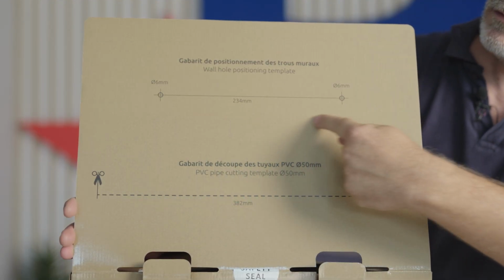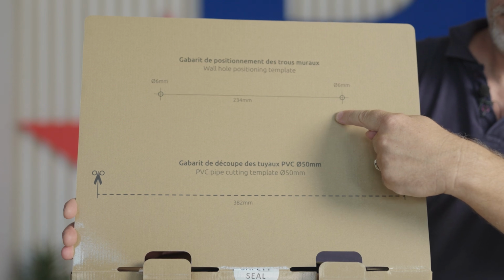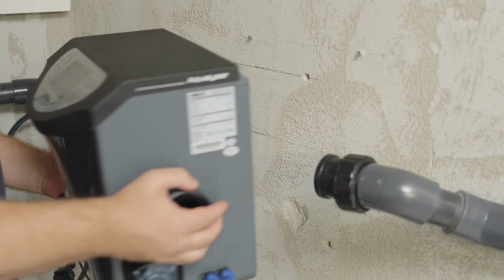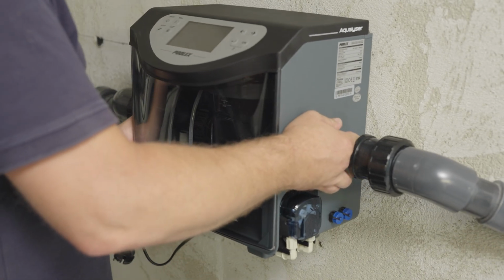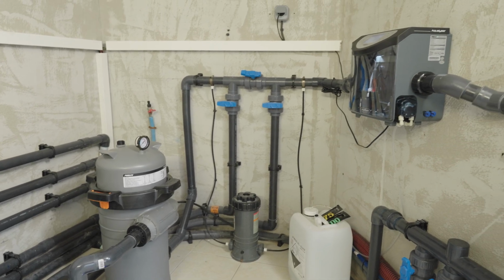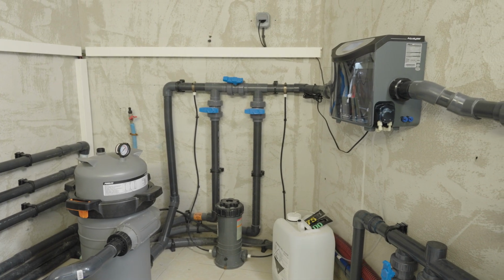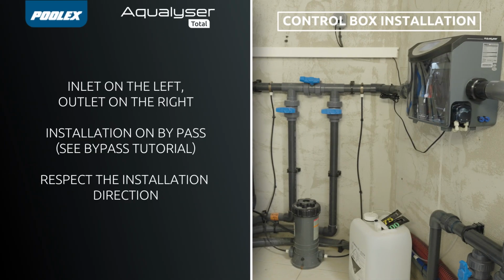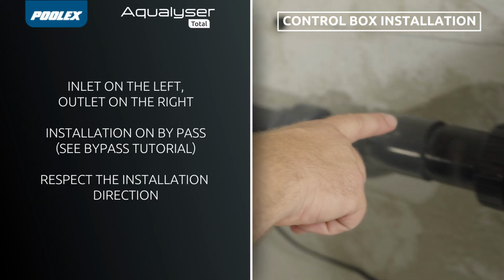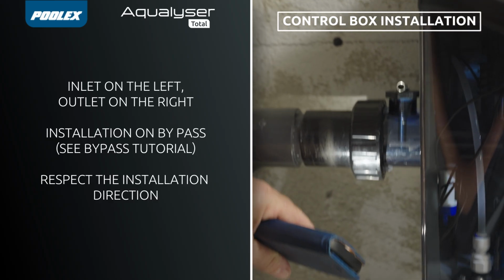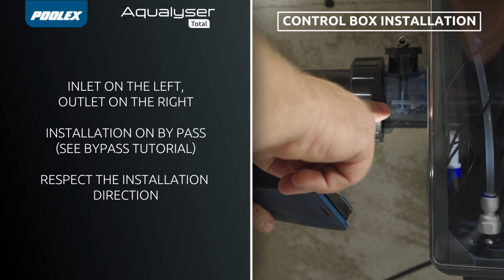Using the drilling template and a level, mark your reference points. Drill the wall, then fix the Aqualyser in the designated spot. Install the Aqualyser Total on a bypass of the return pipe after the heating system. Important: the water inlet is on the left, the outlet on the right. Make sure to respect the circulation direction.